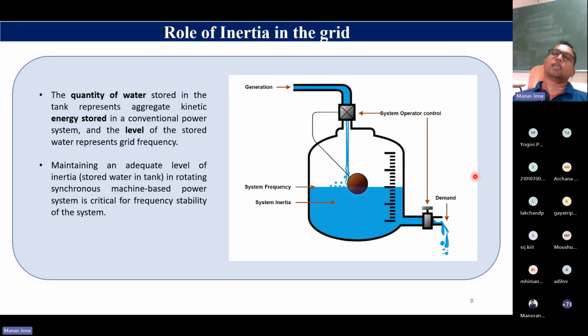Following a contingency, if you have a good amount of inertia in the system, what will happen following the contingency? The frequency nadir point, we use this term called frequency nadir, the lower frequency it will reach. If you have a good inertia, it will be on a higher side. If you have a lower inertia, it will be on the lower side.